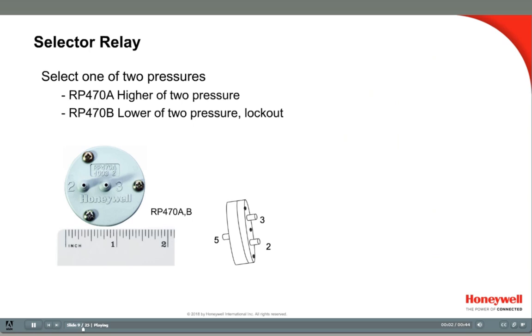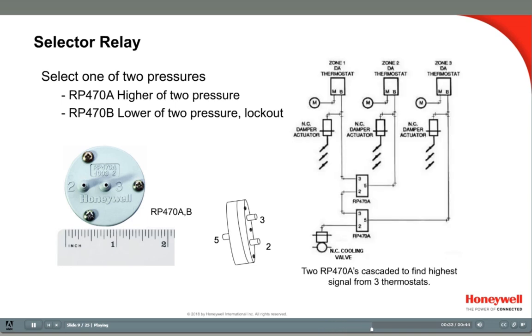Select relays compare pneumatic signals and select the higher or lower input. They have three ports. The RP-470A has two inputs marked 3 and 5. These two inputs are compared, and one outlet marked with a 2. The input that is highest is allowed to pass through to the outlet. The RP-470B selects the lower of two pressures. Ports 2 and 5 are the inputs and port 3 is the output. The RP-470B can also lock out one pressure signal when a second signal is higher. In this example, two RP-470As are used to select the signal from the thermostat calling for the most cooling, and that stat will then control the cooling valve.